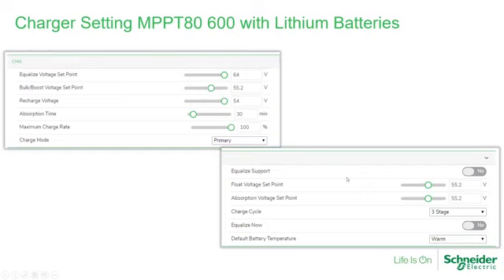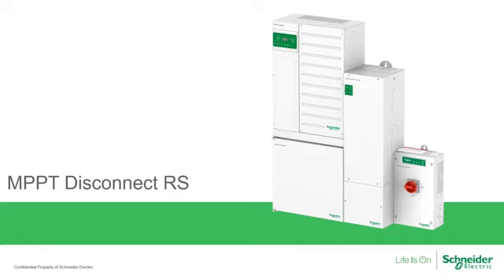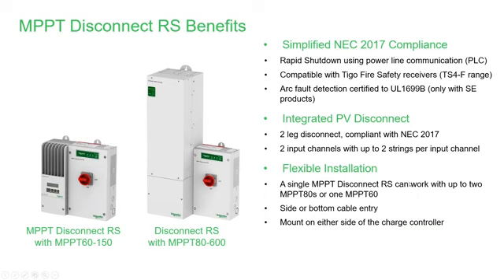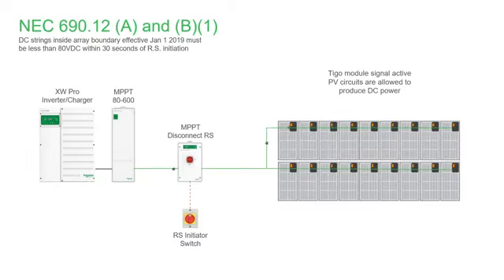Okay? And the last thing I want to touch on is for you guys in the North America region with requirements for rapid shutdown, NEC 2017, rapid shutdown. So we meet 690.12, which is rapid shutdown, as well as 690.11, which is arc fault, with our newest MPPT Disconnect RS. So you actually have three things in one with the Disconnect RS. So you have the rapid shutdown, you have the arc fault, and you actually have a PV disconnect.